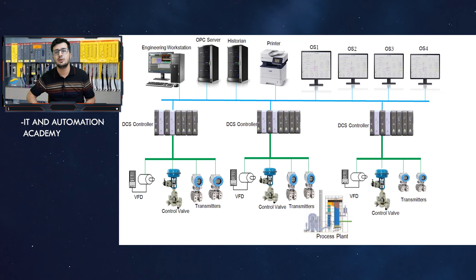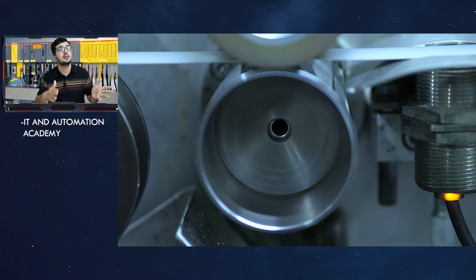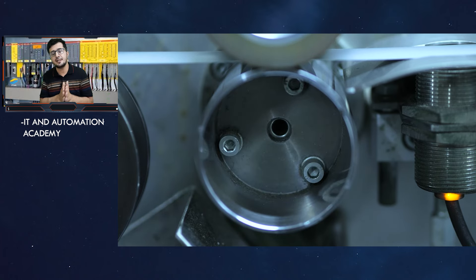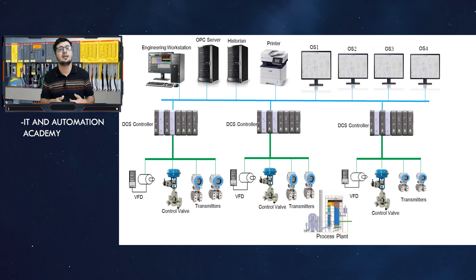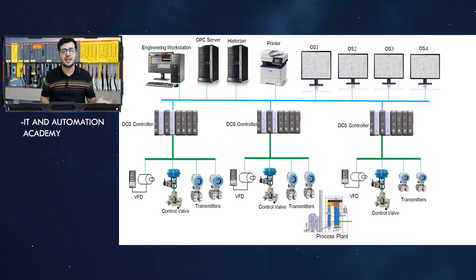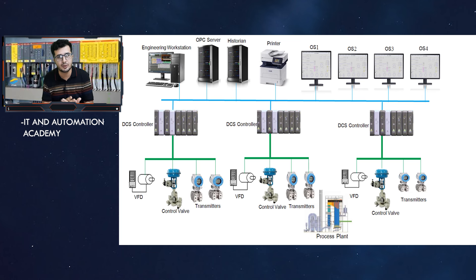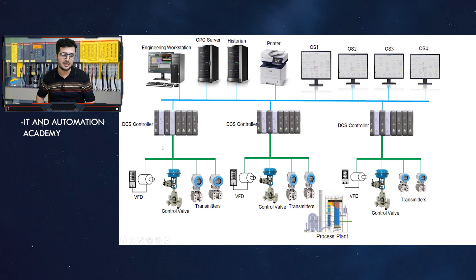These instruments — motors, control valves — are connected to your DCS system. Just like PLCs have IO cards — input and output cards, analog and digital — DCS also has IO cards. Analog signals like temperature, pressure, level, and flow come into analog input cards. Digital signals connect to digital input cards. So the concept is the same as PLC: power supply, input cards, output cards. The signal travels from the field to your DCS controller.